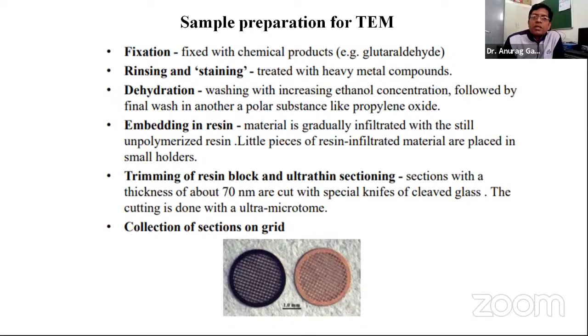Some of the particles of your powder will stick over these grids, and then the grid is placed as a sample, and the electron beam passes through the grid. The grids are already electron transparent because they are meshes with pores. So naturally they are electron transparent, and the particles attached over the grid can be imaged. You can see the image of your powder sample by using this approach. The powder material can be analyzed, and you can see the shape and size of the particles with the help of the grid for transmission electron microscopy.